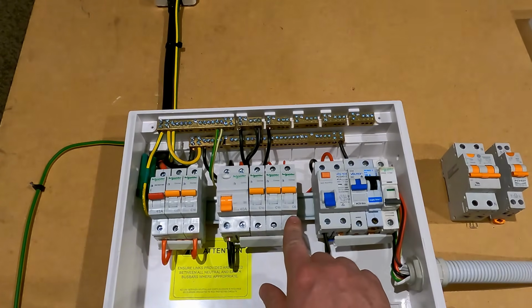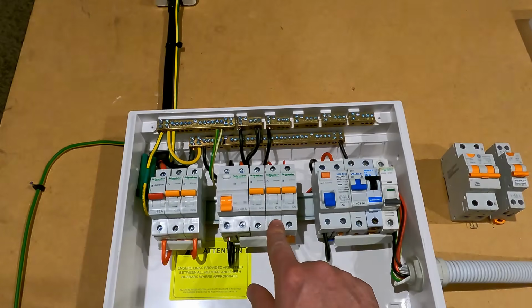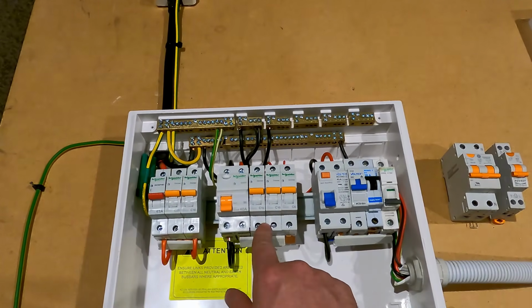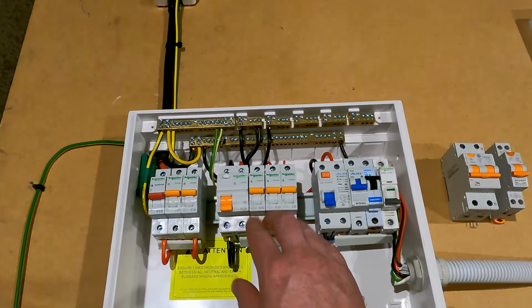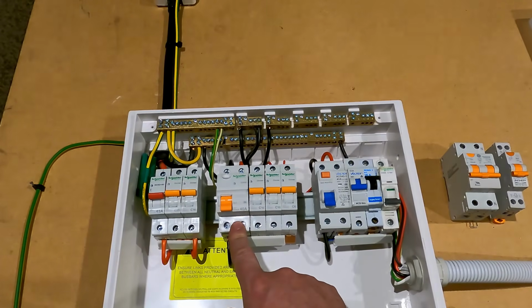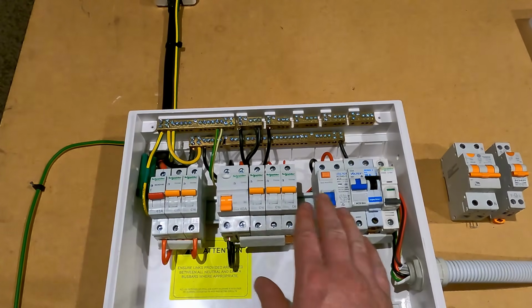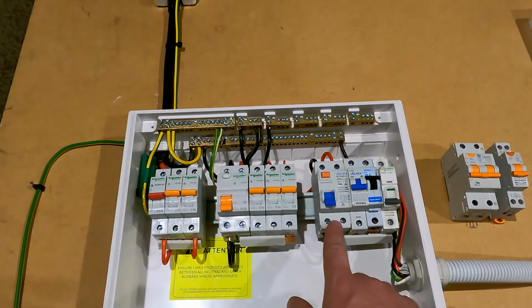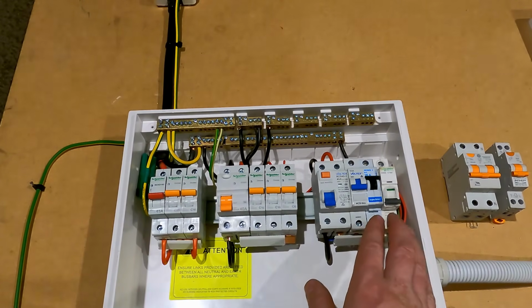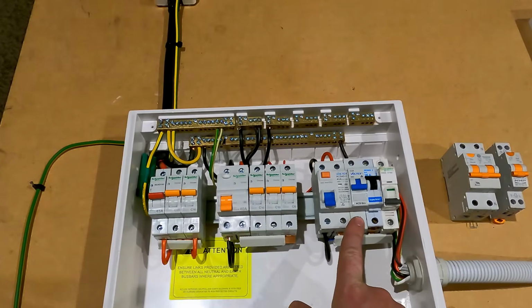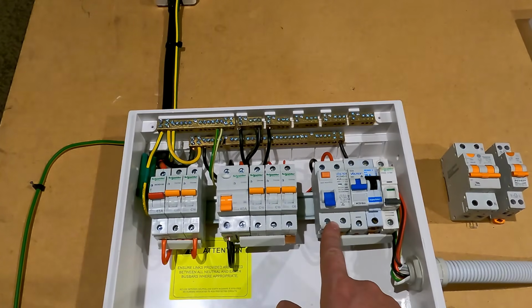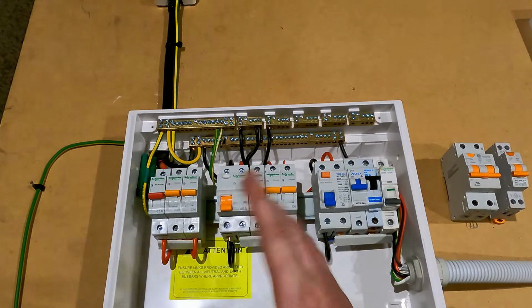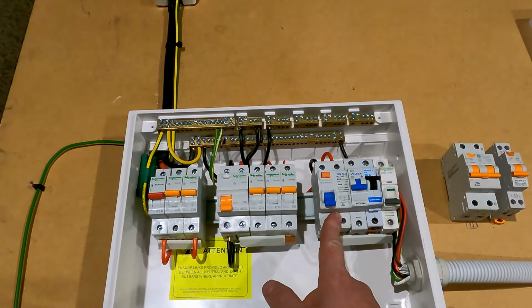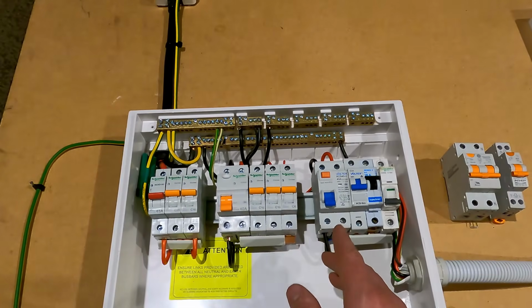So 2 16s and a 6, well 3 6s are 18 plus 20 is 38 amps is the maximum current capacity of these. So on a 40 amp RCD, that's fine. Over here we've got a 40 amp RCD, we've got 2 16s and a 10, and that's 42 amps. So that is too much loading for this 40 amp RCD. So all you'd have to do is just pick up a 63 amp RCD. It's the next available size up.